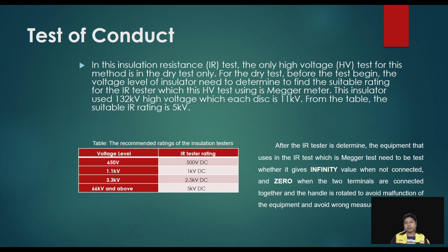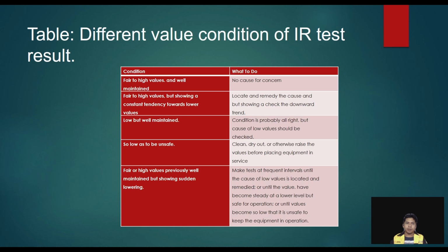So after the IR tester is determined, the equipment used in the IR test, which is a Megger meter, needs to be tested whether it gives an infinity value when not connected, and zero when the two terminals are connected. Together the handle is rotated to avoid malfunction or the equipment giving the wrong measurement. So this is the table for the different value conditions of the IR test.